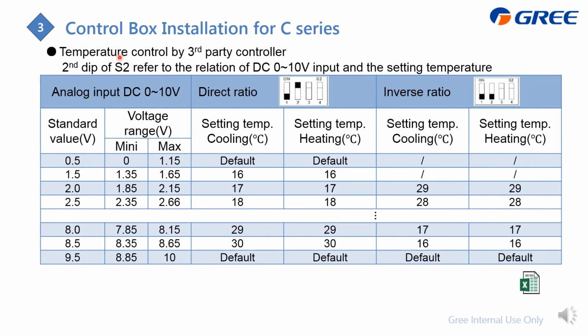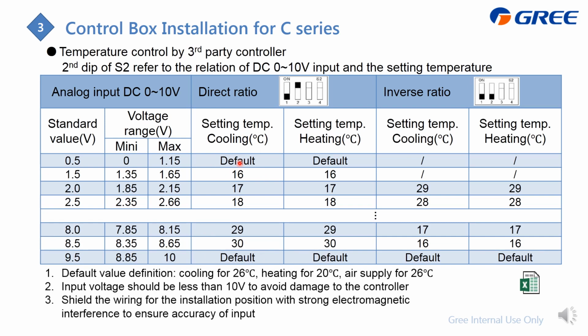As for the temperature control by the third-party controller, according to the relationship, if it is direct ratio, you need to change the second switch of the S2, and if it is reverse, just like this. The relationship is like this one, according to the input voltage and the set temperature. We recognize it as reverse. If you don't have this device, the default values are defined as follows: cooling at 26 degrees, heating at 20 degrees, and air supply at 26 degrees. The input voltage of this temperature control should be less than 10 volt to avoid damage to this controller.